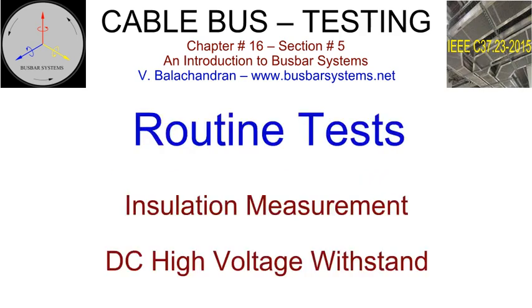Routine tests. The assembly of the cable bus is carried out only at the installation site. After the installation and before commissioning, the following routine tests need to be carried out. Insulation measurement of cables with a tester of recommended voltage. Specified DC high voltage withstand test.